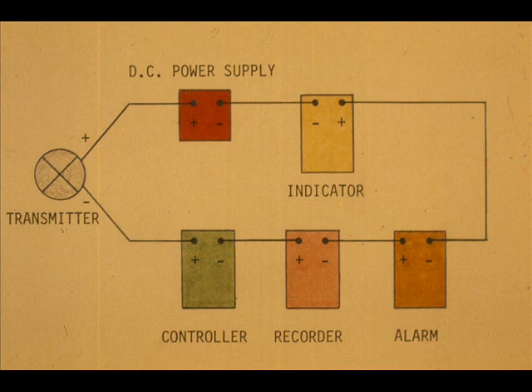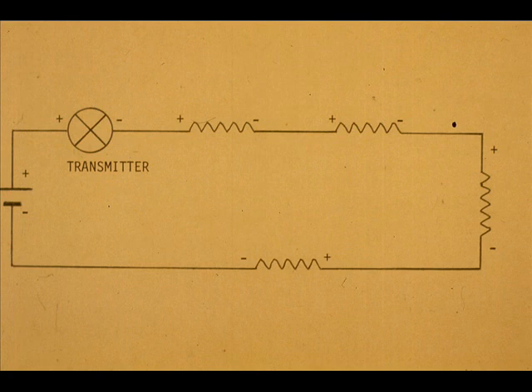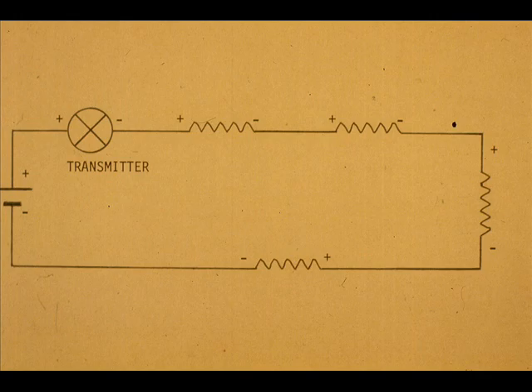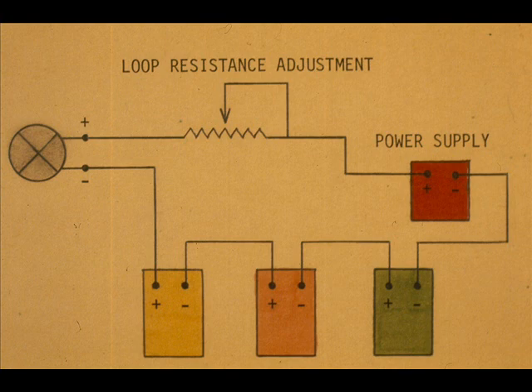Depending on the manufacturer, the loop components other than the transmitter may be hooked in series. The series system can be compared to a battery and resistor circuit, where the resistors represent the loop components. Controllers, many recorders, and other components are actually voltmeters that measure voltage drops across their respective loop resistors. Some recorders in use are current devices and perform like ammeters. The series loop is sensitive to the total loop resistance. When an item is added or subtracted, the total loop resistance is maintained correct by adjusting the variable resistor.